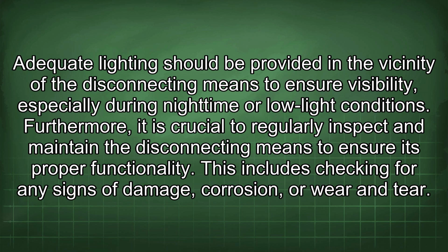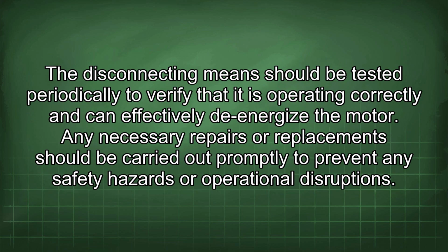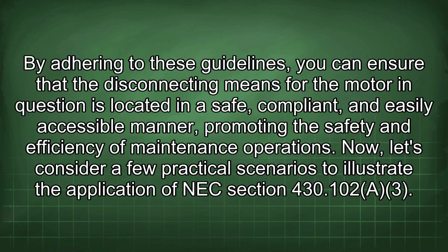This includes checking for any signs of damage, corrosion, or wear and tear. The disconnecting means should be tested periodically to verify that it is operating correctly and can effectively de-energize the motor. Any necessary repairs or replacements should be carried out promptly to prevent any safety hazards or operational disruptions. By adhering to these guidelines, you can ensure that the disconnecting means for the motor in question is located in a safe, compliant, and easily accessible manner, promoting the safety and efficiency of maintenance operations.